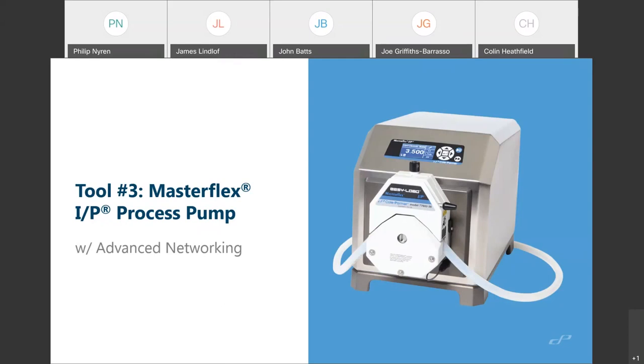It's got a 316 stainless steel casing with an aluminium anodized base. That means your casing is going to ensure that it fits in with your hygienic environment, with your washdown environment, and 316 stainless steel won't show corrosion or rusting. So this does tick the boxes in terms of fitting into your environment. But it's also got, coupled with, the controls, as you've had previously on the front, for the standard setting for dose, dispense, time, flow rates, etc.